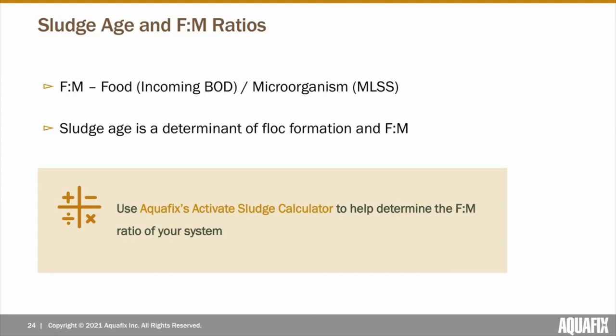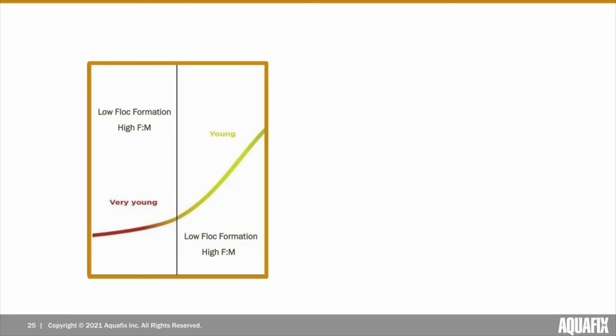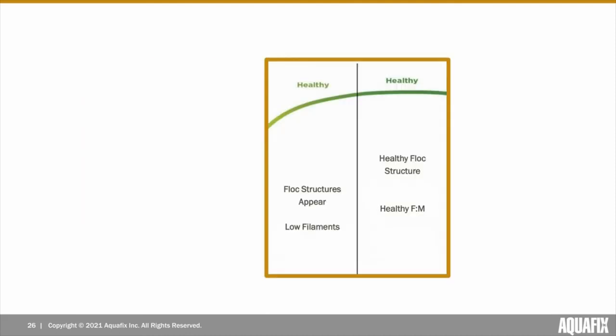Sludge age is also associated with the F to M ratio of a wastewater treatment system — the ratio of incoming food or influent BOD compared to the total number of microorganisms within a treatment plant. At a younger sludge age, we'll have a relatively low population of bacteria as the growth process is starting, and high F to M values as there is more proportional food coming in. Once the sludge age reaches a relatively healthy age, flock structures will become more ideal and the F to M ratios will be healthy. The ideal F to M ratios can vary in every plant.